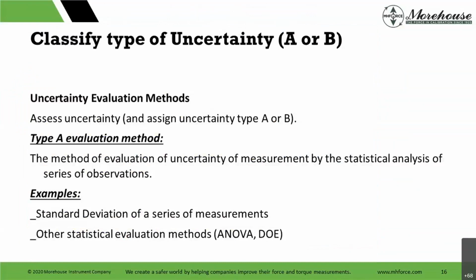Basically, the type A method is evaluation of uncertainty of measurement by statistical analysis. This would be what we were talking about earlier, the precision. If we take multiple measurements and take the standard deviation of it, that would be a type A. Another statistical method I like a lot in Excel, where you normally need to install the advanced pack, is ANOVA, which is an analysis of variance. It's a really useful tool for testing: is it equipment, is it operators? You can do 1-factor, 2-factor.